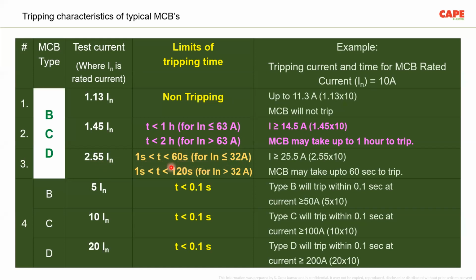And in case of higher than 32 amps, 1 second to 120 seconds. These are the disconnection times. Now, in a type B MCB, if the current is 5 times the IN, it trips within 0.1 second. C type, 10 times IN, 0.1 second, then 20 times IN, again, the disconnection times are quite quicker. So when we select the devices, we have to keep these particular parameters very much in our mind.